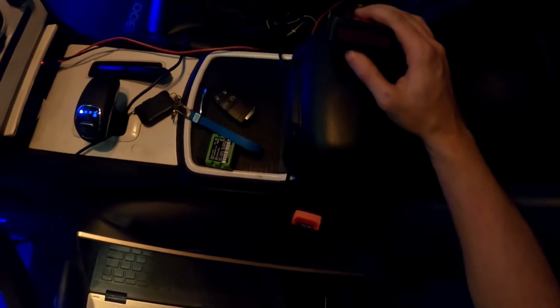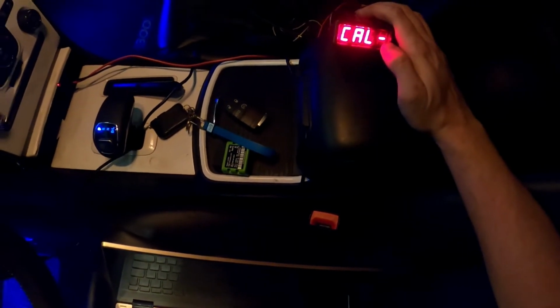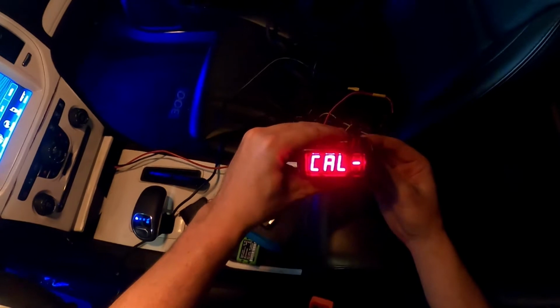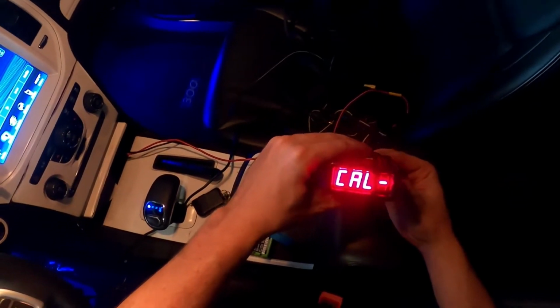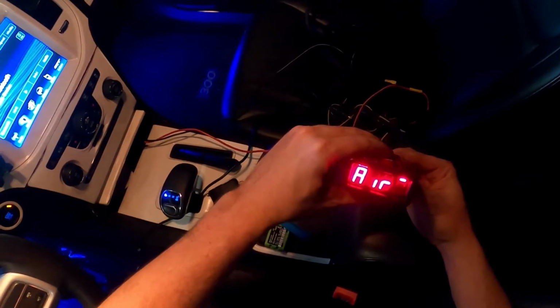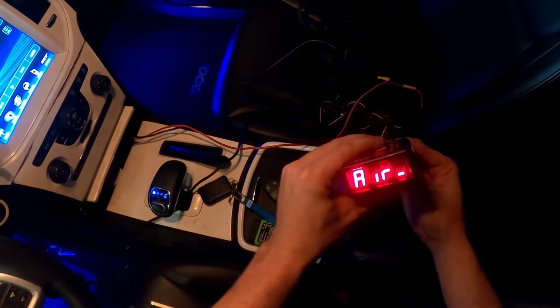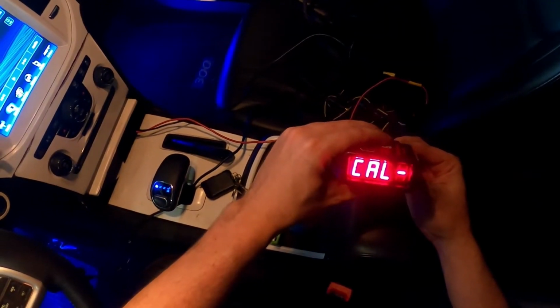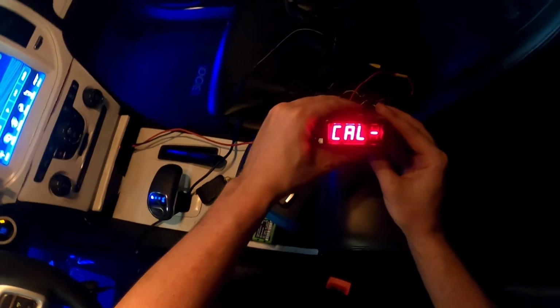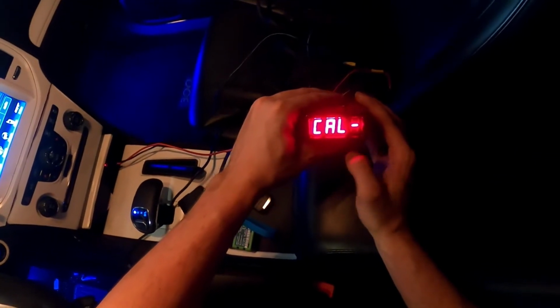After this countdown's done, it's going to tell us the calibration is right in the middle. If you wanted to adjust or recalibrate it, you'd turn the screw in the back—too far one way, too far the other way. So we're going to put the screw right in the middle, giving us the most accurate calibration.